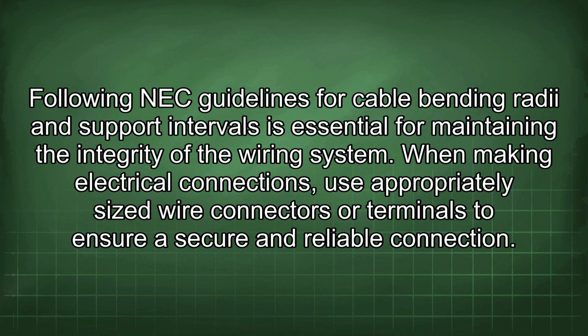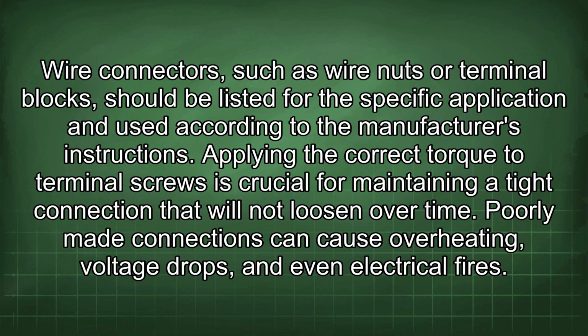When making electrical connections, use appropriately sized wire connectors or terminals to ensure a secure and reliable connection. Wire connectors, such as wire nuts or terminal blocks, should be listed for the specific application and used according to the manufacturer's instructions. Applying the correct torque to terminal screws is crucial for maintaining a tight connection that will not loosen over time. Poorly made connections can cause overheating, voltage drops, and even electrical fires.